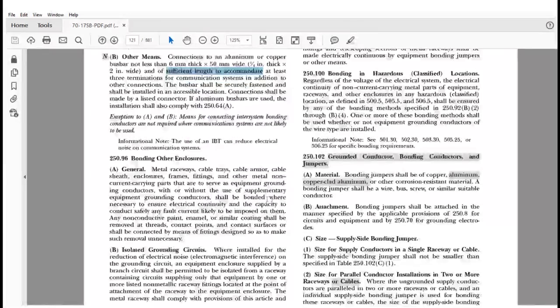The good news here, they did add an exception to the rule. The exception to both A and B says means for connecting inter-system bonding conductors are not required where communication systems are not likely to be used. So if you have a certain type of structure, a structure defined by the code, where you have to have this type of connection for this inter-system bonding connection, you don't need it if you're not really going to require it, or it's not likely to have the need for this type of system.